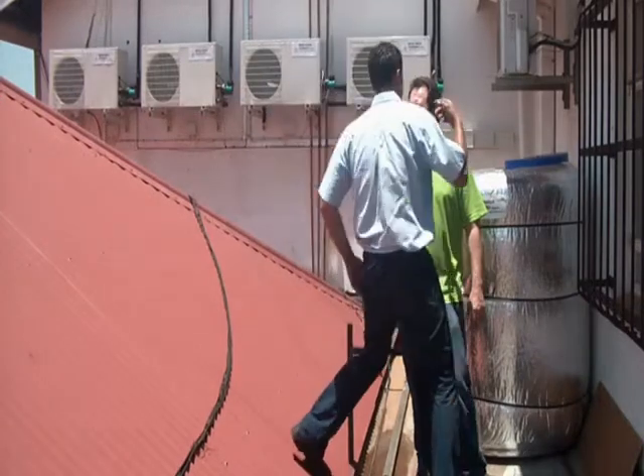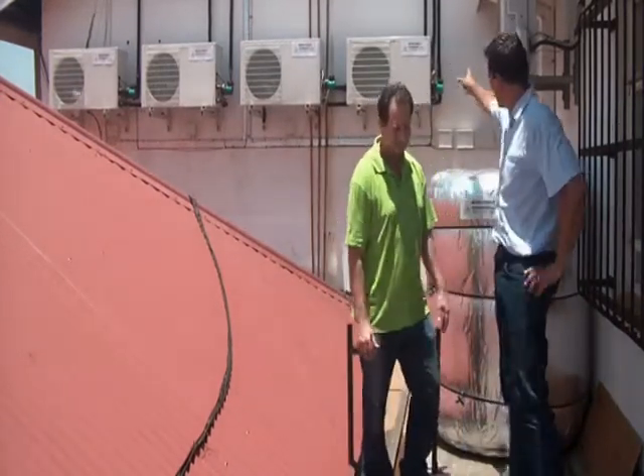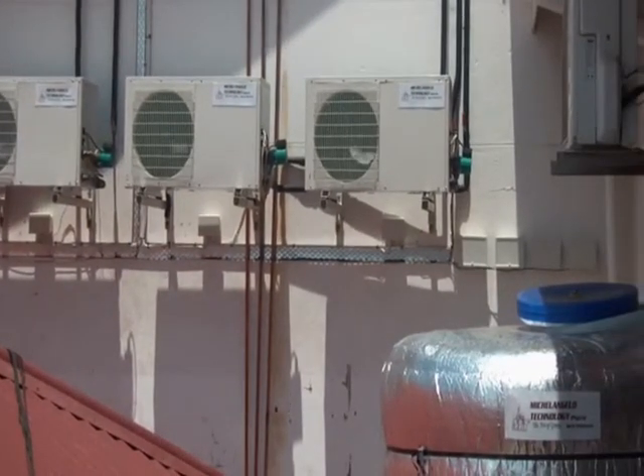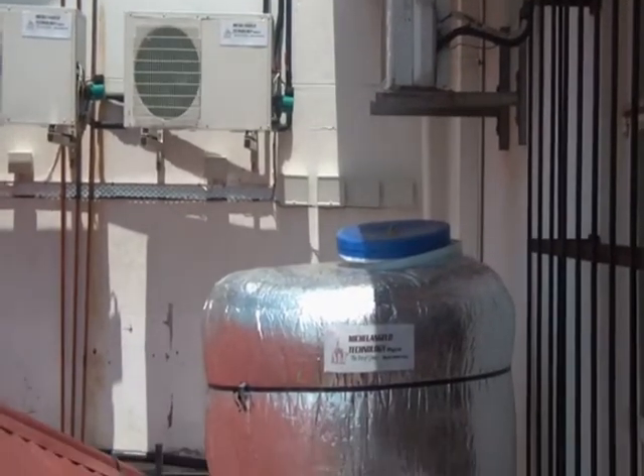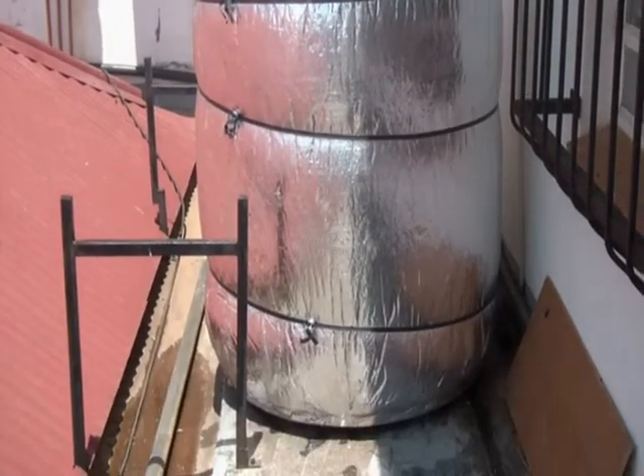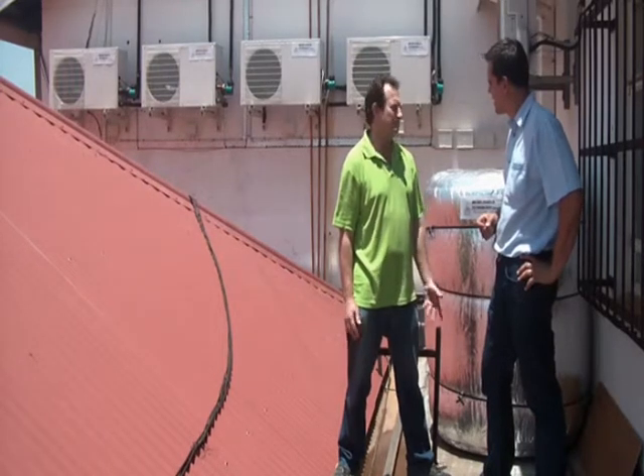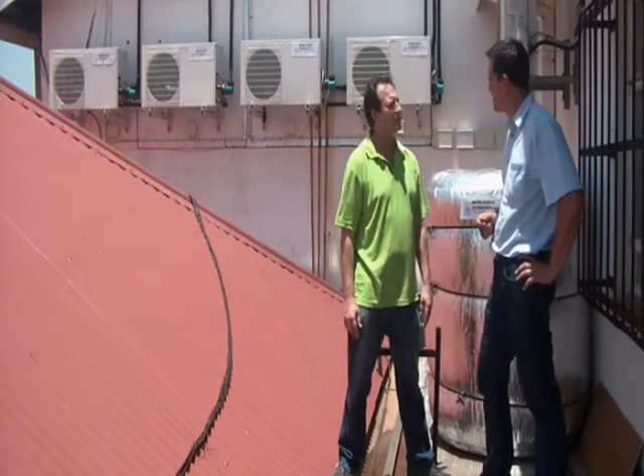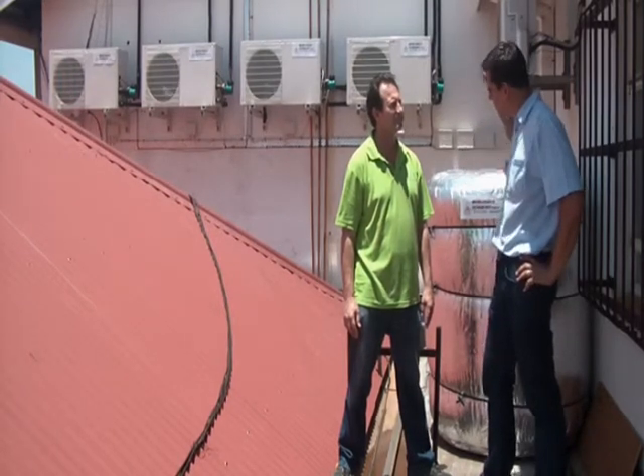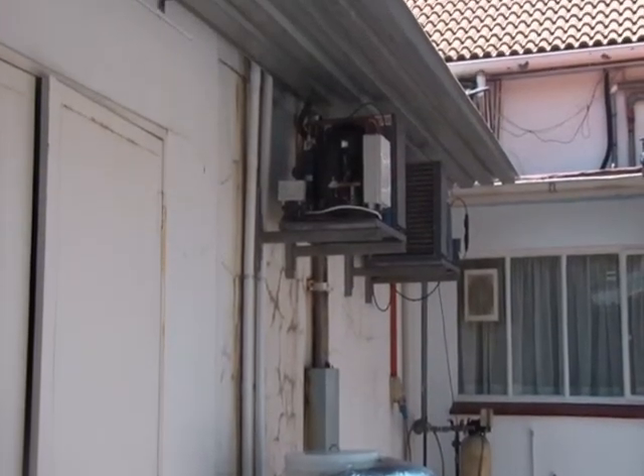With this specific setup, we've got our 1000-litre tank here, which is for storage for the heat pumps. Here you've got four heat pumps connected. And on this same tank you've also got a solar hybrid system. On the roof we have four solar panels, which can do the heating for us. And then there's also a 500-litre system on heat pumps for pre-feeding of the kitchen and the geese units.